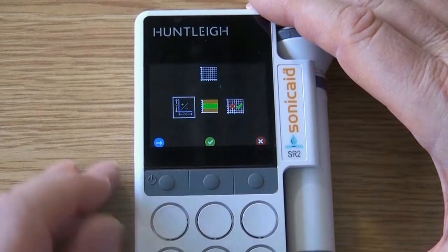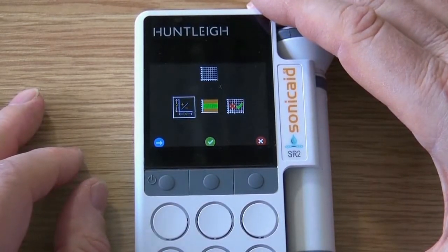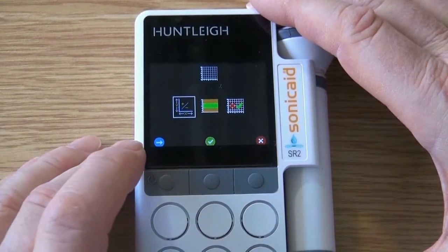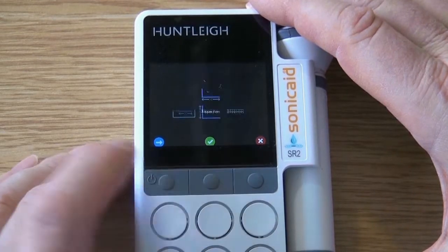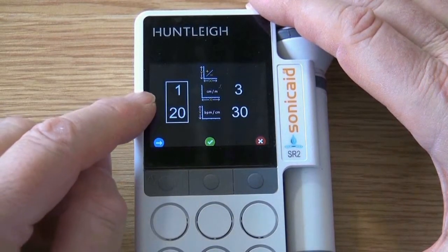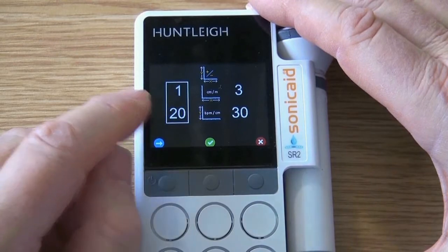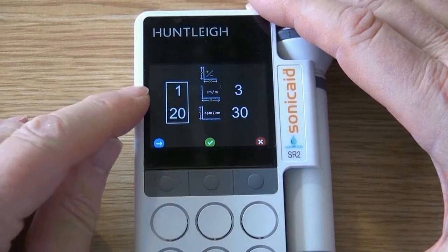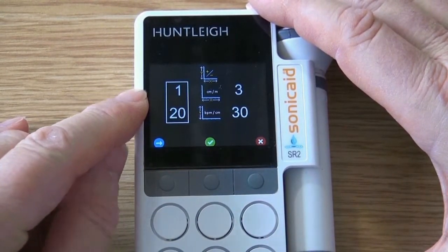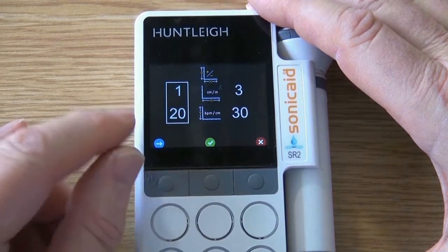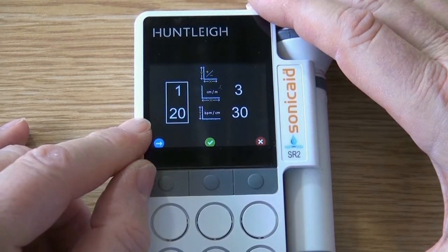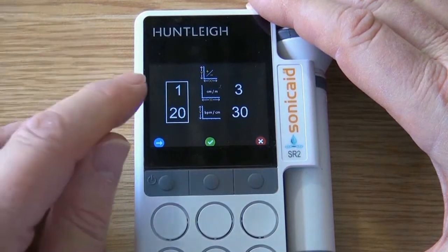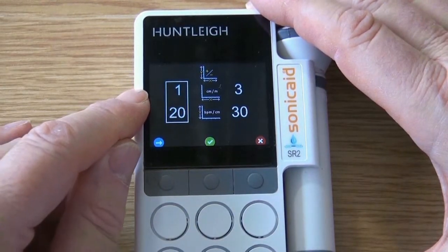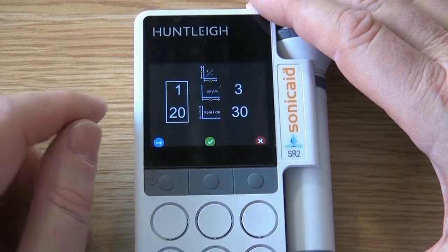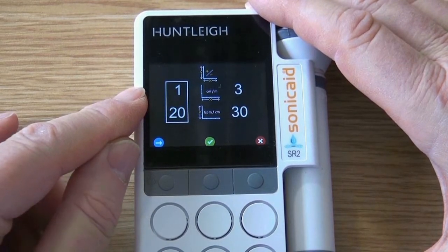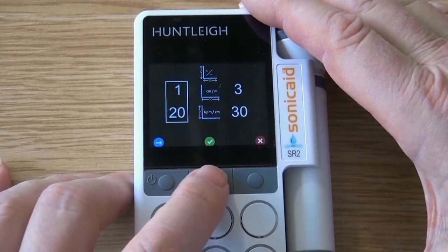With the graph icon highlighted, press the middle button. Press the middle button again, and you are now able to set the vertical and horizontal scaling. The top number stands for 1 centimeter per minute equivalent, and the bottom number of 20 beats per centimeter vertical scaling. These are used throughout most of the world. Press the left button if you wish to change to 3 centimeter per minute horizontal scaling and 30 beats per centimeter vertical scaling. Press the green tick to accept.